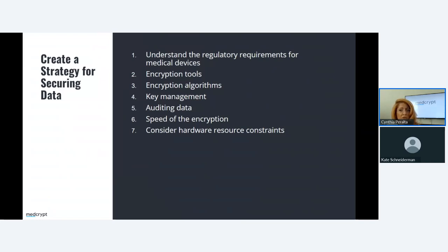We need to create a strategy for securing data and the medical devices. Understand the rules and regulations, which is that the FDA regulates the manufacturers of medical devices, while OSHA regulates the employers, for example. It is the employer who must ensure that the medical device meets the requirements of Subpart S. There are several ISO standards for medical devices here, but we're not going to talk about that here.